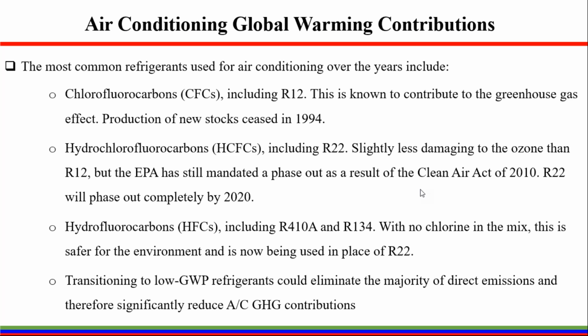The most common refrigerants used for air conditioning over the years include the chlorofluorocarbons, including R12. This is known to contribute to the greenhouse gas effect. Its production for new stock has been ceased since 1994. Hydrochlorofluorocarbons, including R22, are slightly less damaging to the ozone than R12, but the EPA has still mandated a phase out as a result of the Clean Air Act. So R22 will phase out completely during 2020.